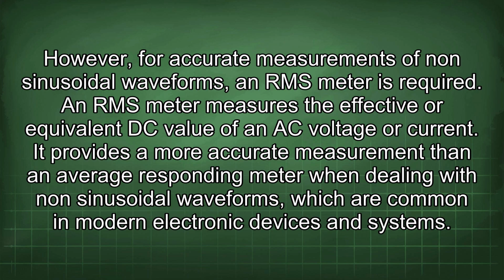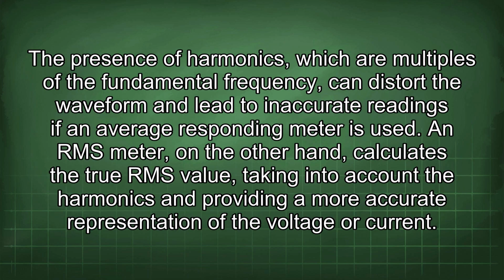An RMS meter measures the effective or equivalent DC value of an AC voltage or current. It provides a more accurate measurement than an average responding meter when dealing with non-sinusoidal waveforms, which are common in modern electronic devices and systems. The presence of harmonics, which are multiples of the fundamental frequency, can distort the waveform and lead to inaccurate readings if an average responding meter is used. An RMS meter, on the other hand, calculates the true RMS value, taking into account the harmonics and providing a more accurate representation of the voltage or current.